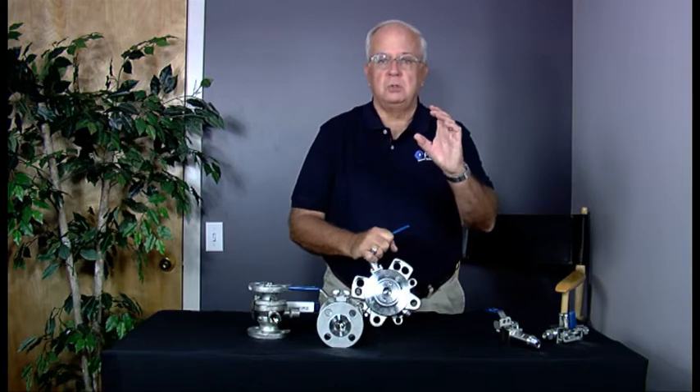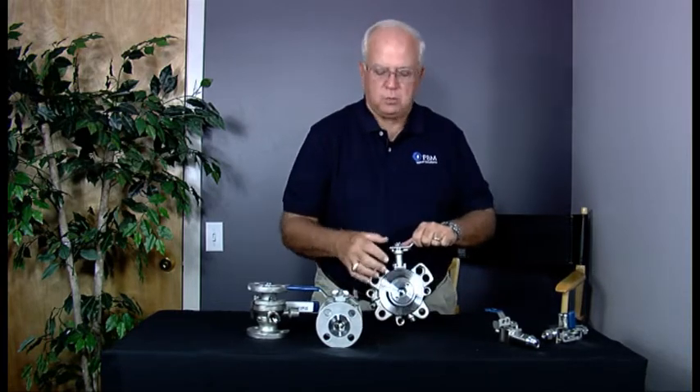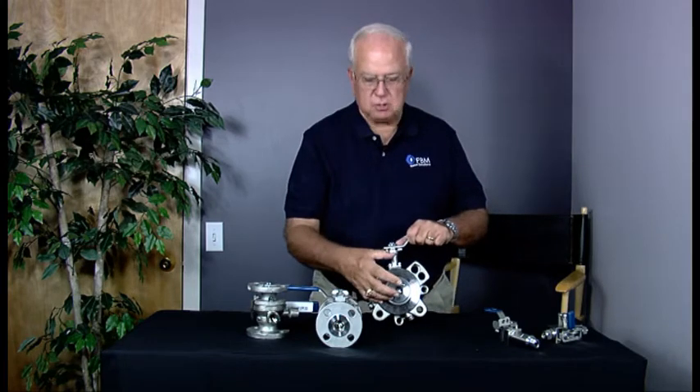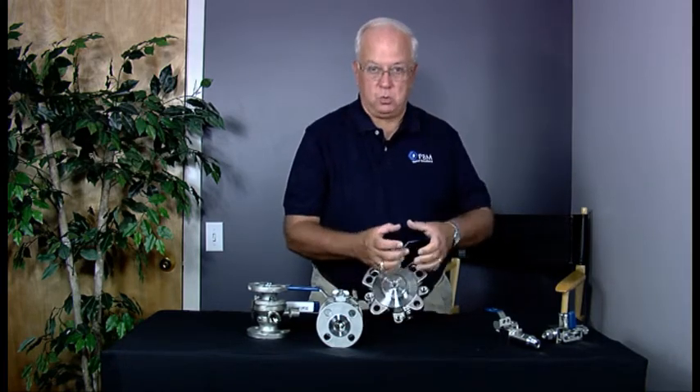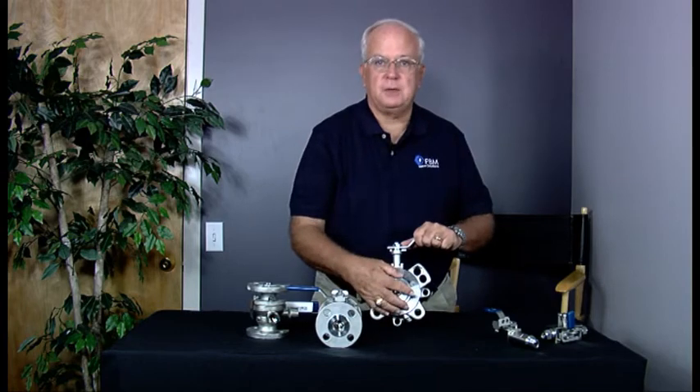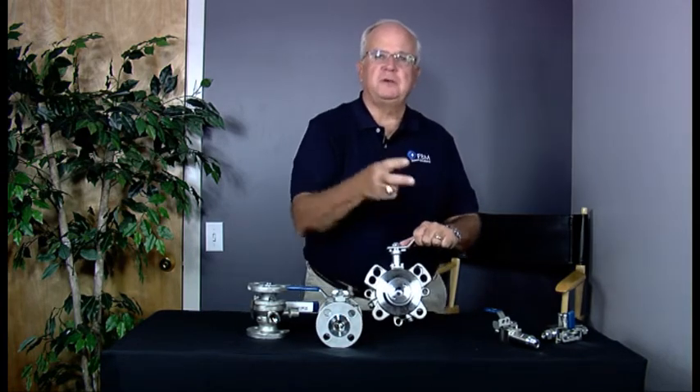However, you didn't need a three-inch hole. This is not a flowing valve — it's essentially a garage door, just shutting off the fluid pressure from the tank to the transmitter so it can be sensed. In liquids, we supply a valve with a one-inch ball and a one-inch hole. In heavier solutions — whether it's pulp stock, hydrocarbon, or whatever it might be — we use a larger two-and-a-half-inch ball with a two-and-a-half-inch hole, so the body becomes longer rather than wider. Those are the two sizes for the two different applications: liquids and more solids or entrained solid-type thicker materials.